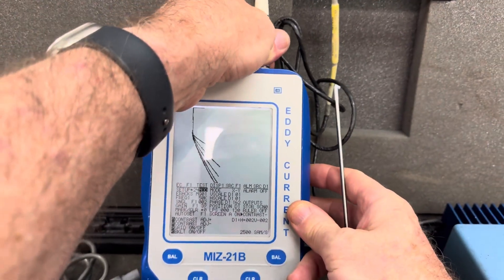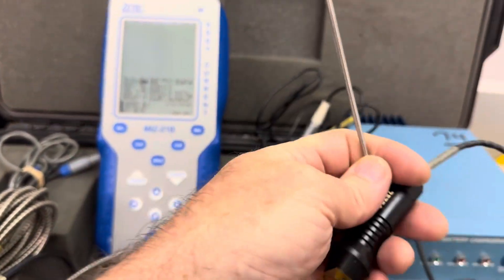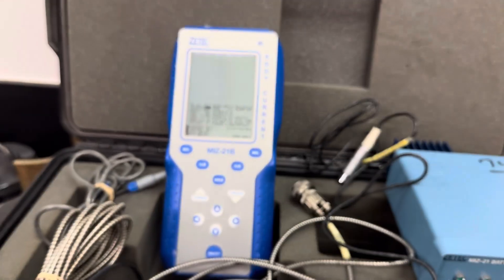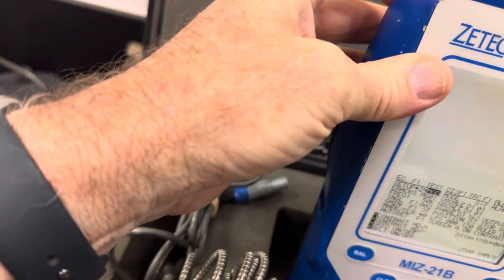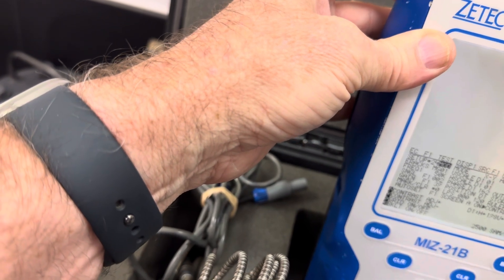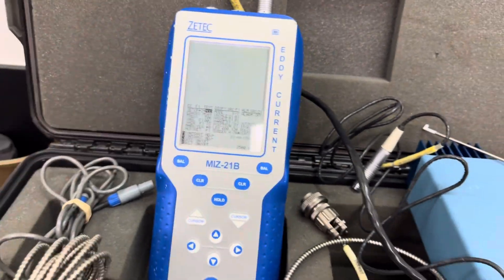There's one. I'm going to take this probe out. In this cable there's a little notch, so you can only put the probe in one way. Push it in. I'm going to make sure that we've attached the probe with the red dot towards the front, which is right like so.